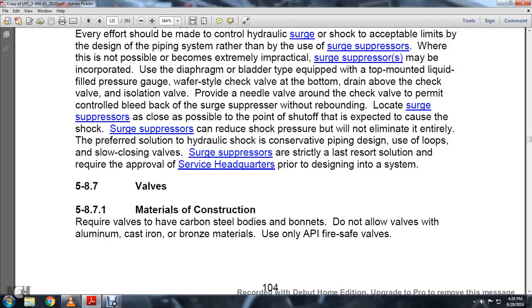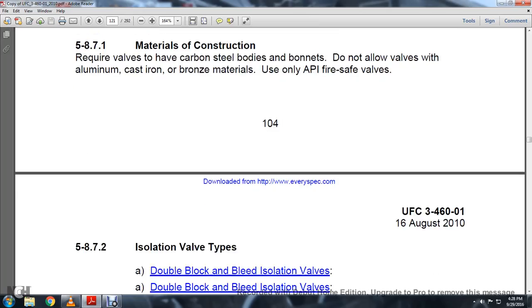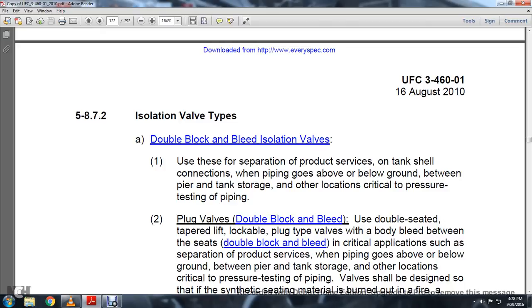5.8.7 Valves. 5.8.7.1 Material construction. Require valves of carbon steel bodies with bonnets. Do not allow valves in aluminum, cast iron, or bronze materials. Use API fire safe valves. Isolation valves, double block and bleed isolation valves.